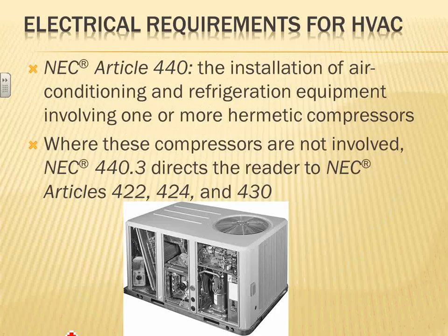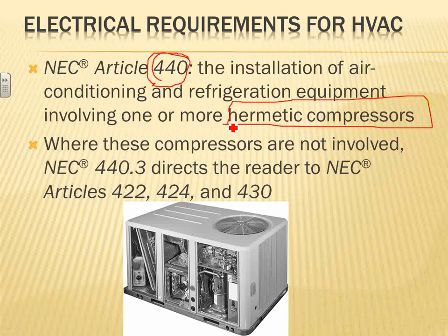Okay, so I just picked a couple of condensers. I picked this equipment, guys, because I thought it's very important for HVAC equipment. If the equipment has a hermetic compressor, then you apply Article 440. Refrigeration equipment, if you do manufacturing, all refrigeration equipment, is the same thing. We size them that way because they have a hermetic compressor, that motor that's sealed together and cooled by the process of refrigeration, then you have to apply this one. Otherwise, you apply Article 430 to all the motors.